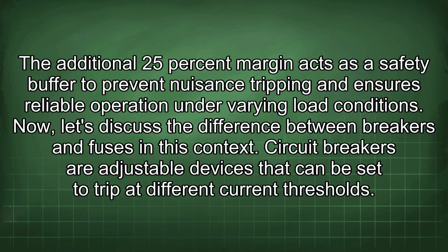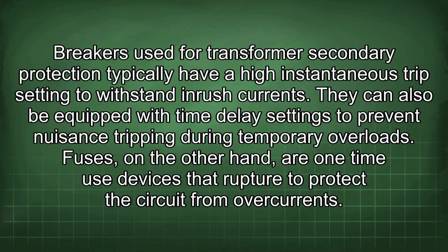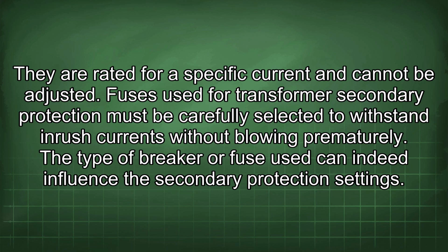Circuit breakers are adjustable devices that can be set to trip at different current thresholds. Breakers used for transformer secondary protection typically have a high instantaneous trip setting to withstand inrush currents. They can also be equipped with time delay settings to prevent nuisance tripping during temporary overloads. Fuses, on the other hand, are one-time use devices that rupture to protect the circuit from overcurrents. They are rated for a specific current and cannot be adjusted. Fuses used for transformer secondary protection must be carefully selected to withstand inrush currents without blowing prematurely.